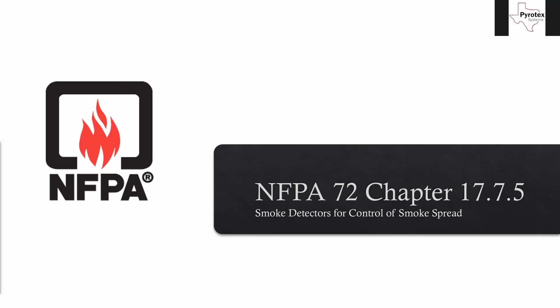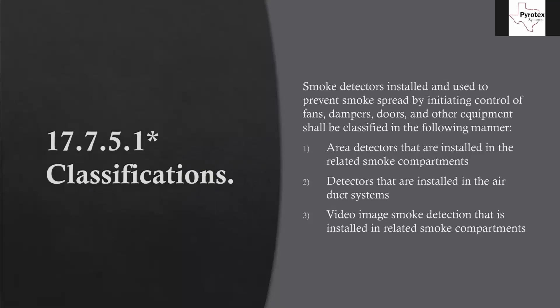Today we're focusing on duct detectors. There are a few classifications for smoke detectors used for preventive smoke spread. Smoke detectors used to prevent smoke spread by initiating control of fans, dampers, doors, and other equipment shall be classified as: area detectors installed in related smoke compartments, detectors installed in the air duct system, or video image smoke detection in related smoke compartments. Today we're focusing on the second one — detectors installed in the air duct system.